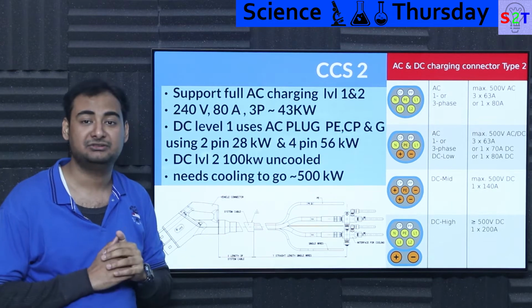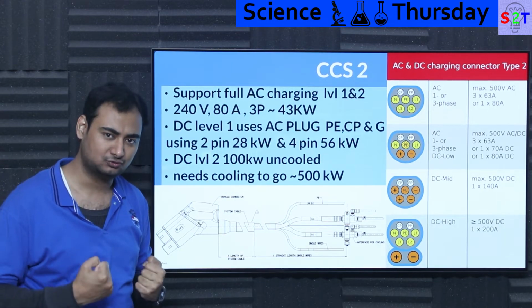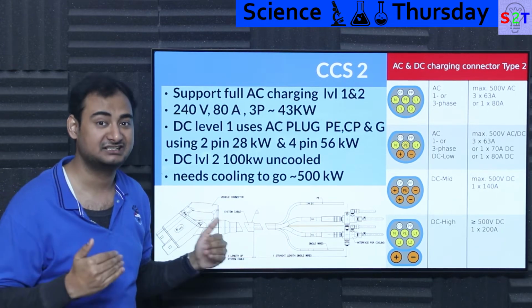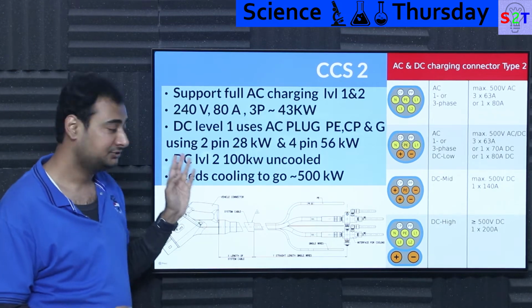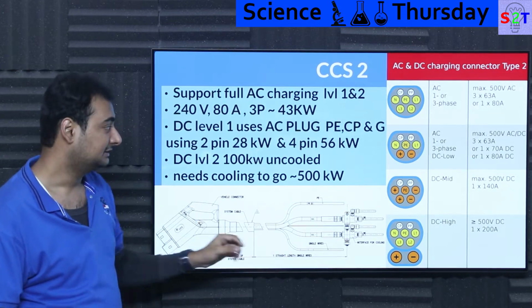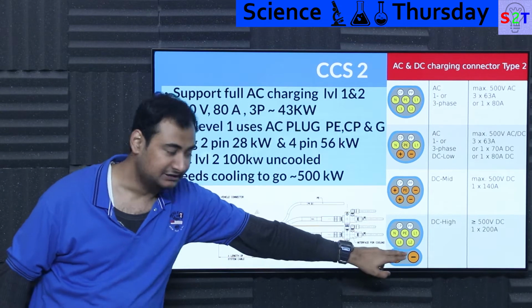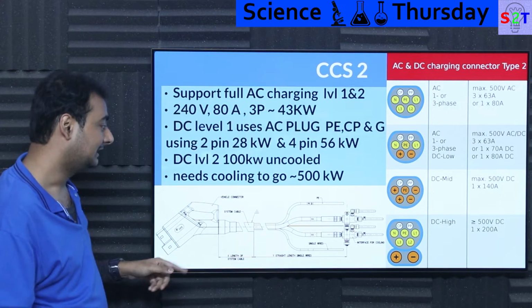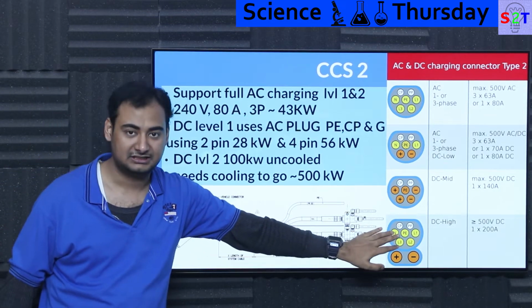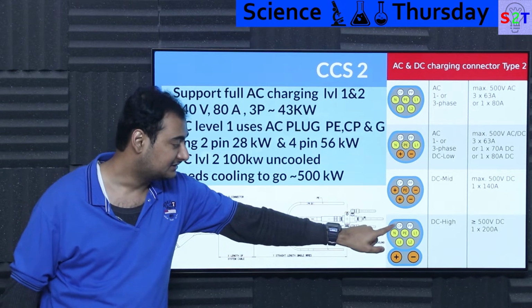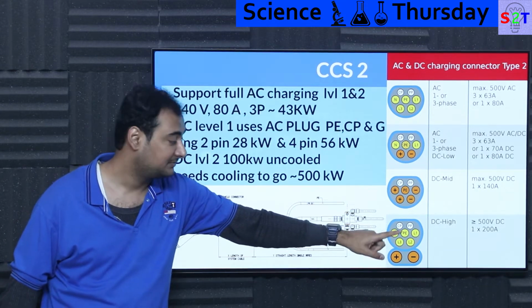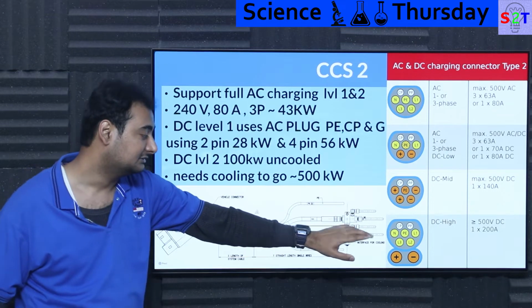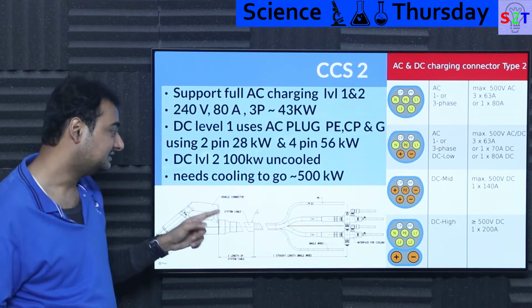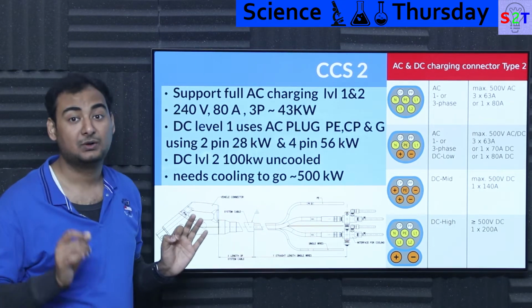But this covers 28 kilowatts and 56 kilowatts. What if you need more? What if you want super duper fast charging, up to 100 kilowatts? At that point you go to DC level 2 — these are level 1, this is level 2 — and you use that thick cable. Again, it won't have all the other pins; basically 4 pins are removed. It'll still have protective earth, contact pin, proximity pin, and DC plus and minus. This connector can dump upwards of 100 kilowatts uncooled.